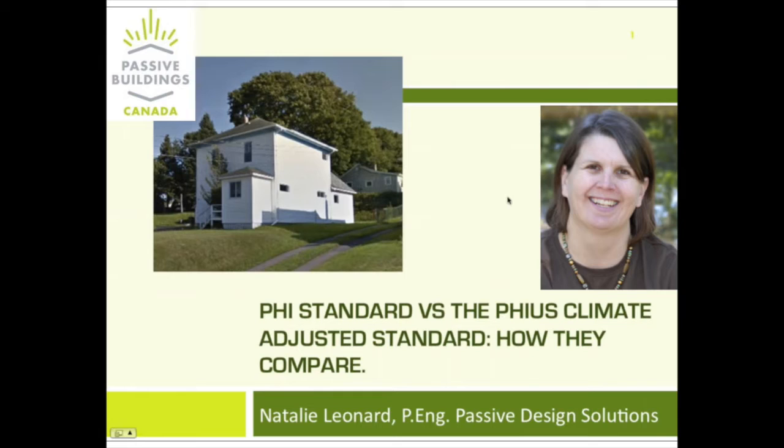It followed the trend that PHIUS reported, that there were higher internal heat gains from plug loads and lights and appliances that were assisting the annual heat demand, but the overall use in the building was very close to target, just a tiny bit over those first 2 years. There's a 4th project that's being monitored in Nova Scotia as well, but it's not occupied full-time, so the data is a little less relevant.